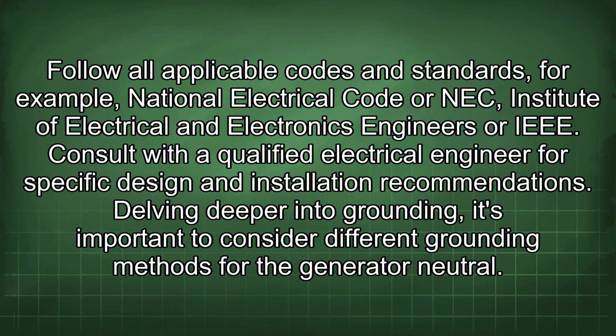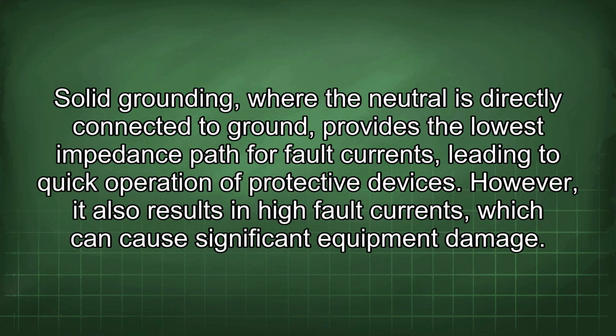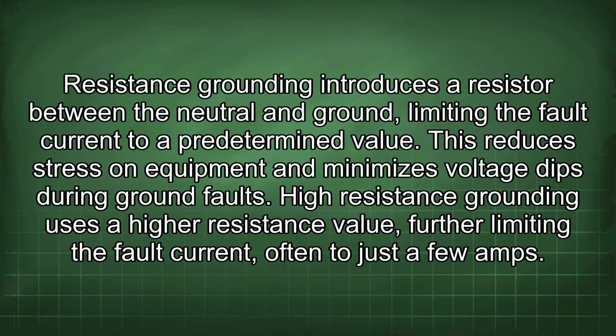Delving deeper into grounding, it's important to consider different grounding methods for the generator neutral. Solid grounding, where the neutral is directly connected to ground, provides the lowest impedance path for fault currents, leading to quick operation of protective devices. However, it also results in high fault currents, which can cause significant equipment damage. Resistance grounding introduces a resistor between the neutral and ground, limiting the fault current to a predetermined value. This reduces stress on equipment and minimizes voltage dips during ground faults.